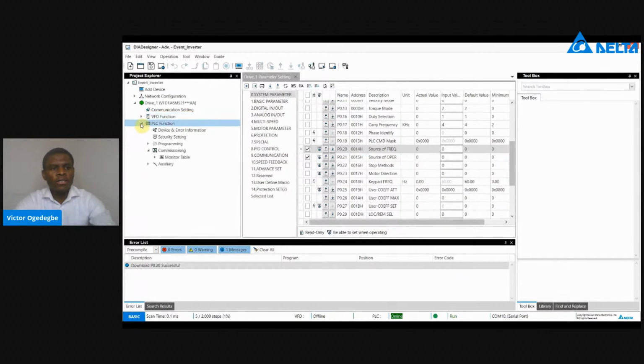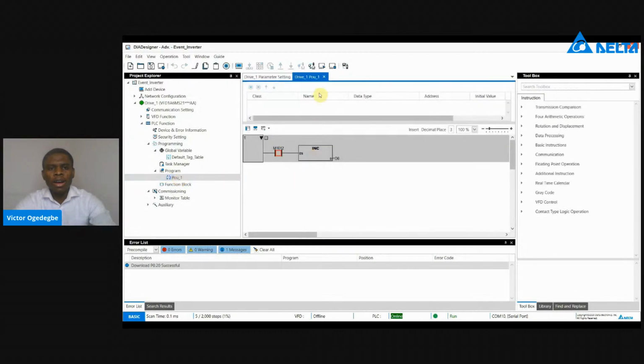If you open the PLC function, go to programming, and then you can see the POU we already made. Click on the POU, and then you can go online. If I go online, you could see that this instruction in the internal PLC of the drive is executing. So this is the first feature I'd like to show to you. One software has programmed the VFD parameter as well as the internal PLC of the VFD.